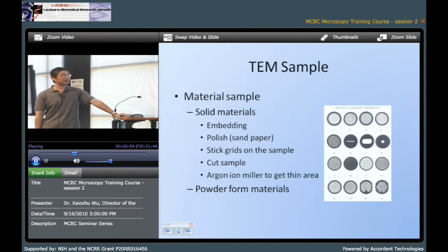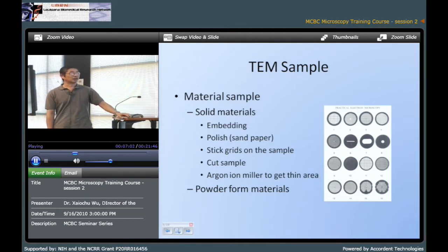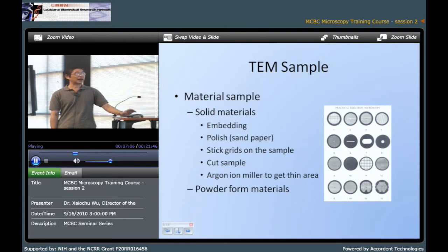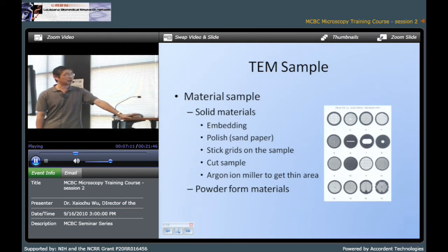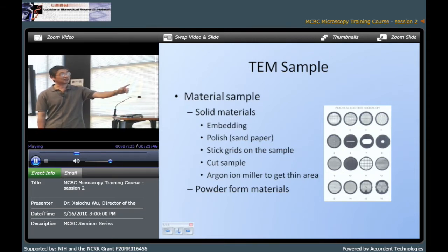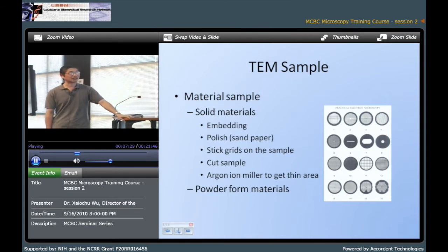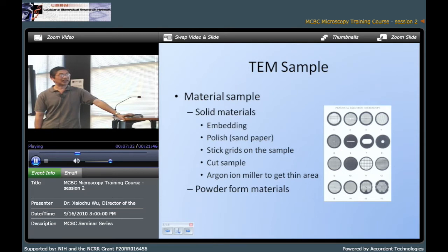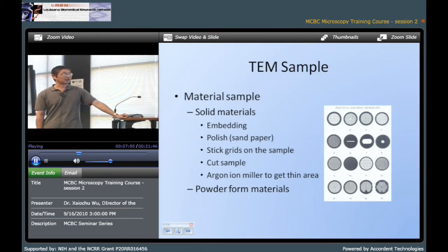For TEM sample preparation it is a little complex, depending on what kind of material you have. For materials science samples, if your sample is solid material, you need to embed your sample, then polish it to about 10 microns maximum. Then you stick the grid on your sample. The grids can be different types and have different sizes — they have 3 mm and 2.3 mm. So you need to ask what kind of grid your TEM uses. After you put your grid on the sample, you need to cut the sample and put it into an ion miller to get a thin area. Usually the ion miller uses argon. If you use powder form material, then it is a little simpler — you just need to put your powder form material on the holey carbon grids.